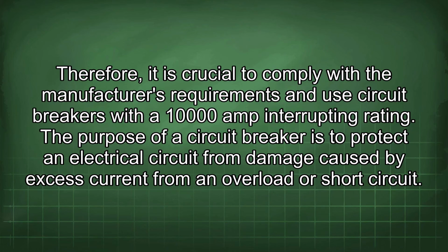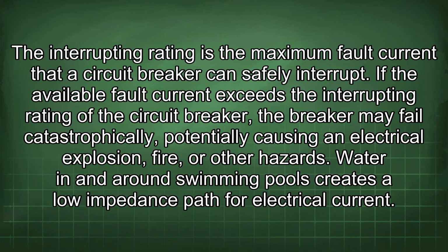The purpose of a circuit breaker is to protect an electrical circuit from damage caused by excess current from an overload or short circuit. The interrupting rating is the maximum fault current that a circuit breaker can safely interrupt. If the available fault current exceeds the interrupting rating of the circuit breaker, the breaker may fail catastrophically, potentially causing an electrical explosion, fire, or other hazards.